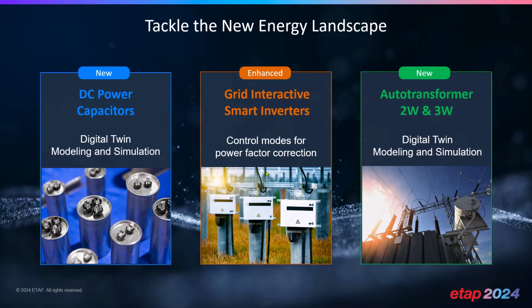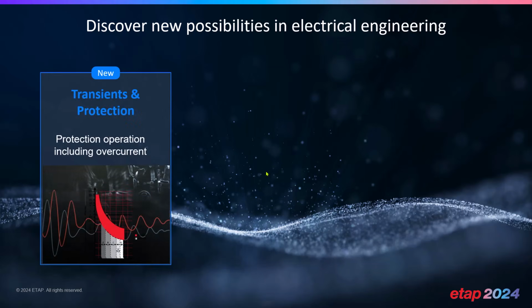We have a brand new module, which is a game changer within our industry. And this module is unified transient and protection. As simply as I can explain it, it allows the combination of dynamic stability analysis with the complete protection evaluation, not just instantaneous, but also overcurrent, distance, out of step, fuses, breakers, relays. Everything is included within this evaluation along with our stability program, which makes it a very unique offering that allows you to do these assessments at a single click.